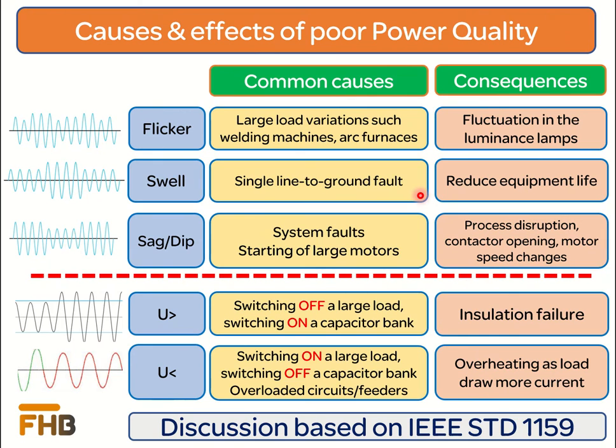The effect of voltage swell on the consumer load largely depends on the frequency of occurrence. Electronic equipment such as computers, electronic controllers, and VFDs may fail due to this phenomenon. Voltage swells can also reduce the life of electrical devices such as transformers, cables, capacitor banks, and electrical motors. Voltage sags are produced by a short circuit fault in the power system, and also due to switching off heavy loads or starting large motors. Voltage sags are dangerous in power systems as process controllers can initiate a shutdown sequence. Magnetic contactors used in different control schemes can get de-energized due to voltage sags, and motors may experience a slight change in speed.